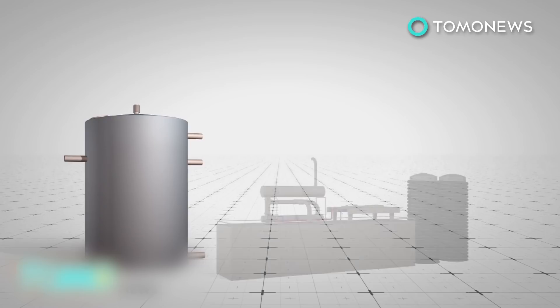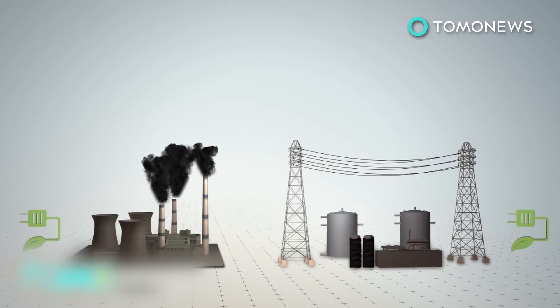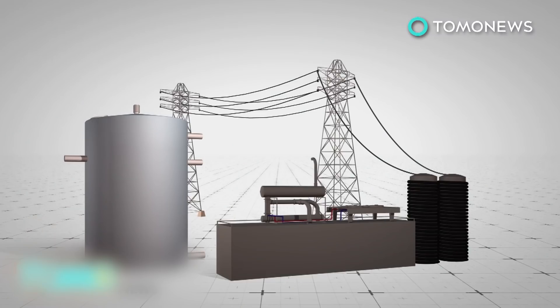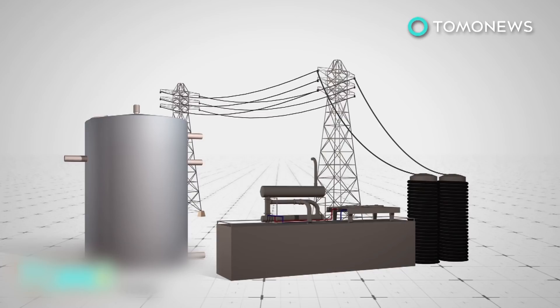A cogeneration power plant produces steam, heat, and electricity simultaneously. It is more efficient than other kinds of power plants and boilers — plants can achieve up to 90% energy efficiency, whereas conventional power plants often achieve just 33%, as most of the heat energy is wasted. The 25-megawatt plant is expected to generate more than 173 million kilowatt hours of electricity a year, and up to 70,000 pounds per hour of steam — all the energy needed to power Los Angeles' Hyperion Water Reclamation Plant.